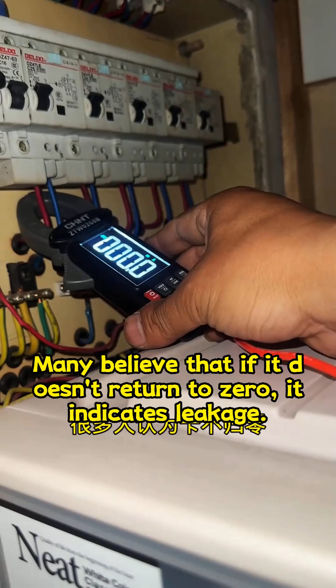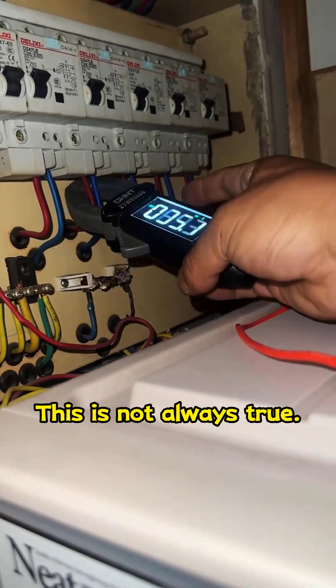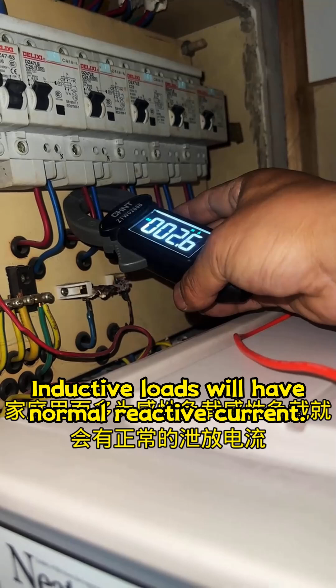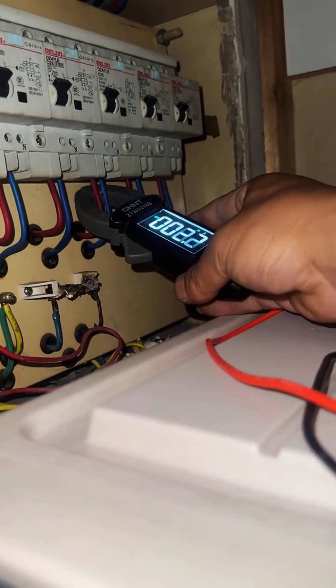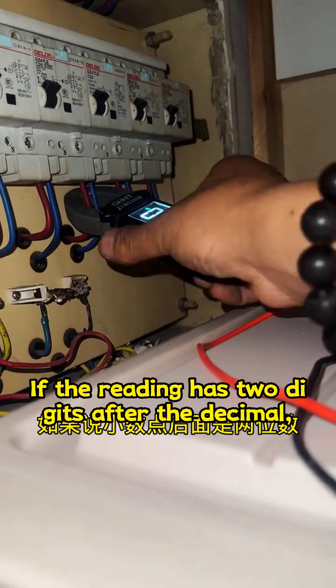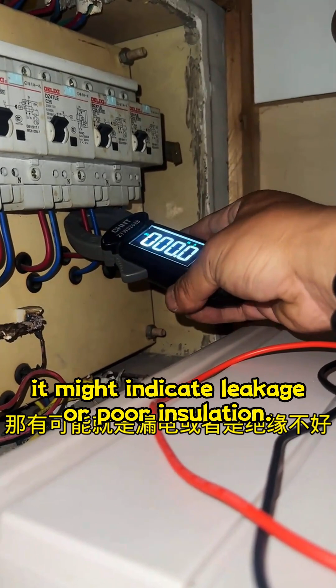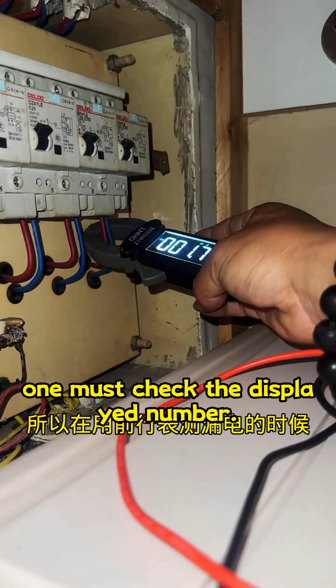What reading indicates leakage? Many believe that if it doesn't return to 0, it indicates leakage. This is not always true. Households often have inductive loads. Inductive loads will have normal reactive current. The induced current can be several milliamperes. These are normal phenomena. If the reading has 2 digits after the decimal, meaning tens of milliamperes, it might indicate leakage or poor insulation. Thus, when using the clamp meter for leakage testing, one must check the displayed number.